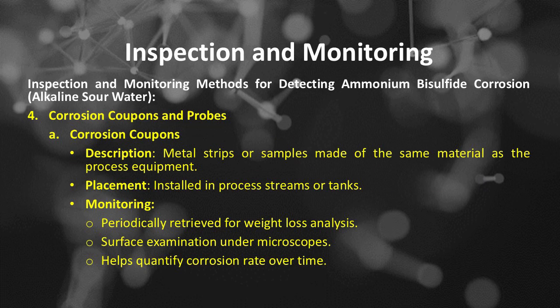Inspection and monitoring methods. Number 4 is corrosion coupons and probes, which includes, number A, corrosion coupons. These are metal strips or samples made of the same material as the process equipment. Corrosion coupons are installed in process streams or tanks, and periodically retrieved for weight loss analysis and surface examination under microscopes. This helps quantify corrosion rate over time.